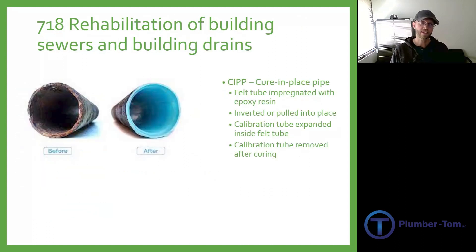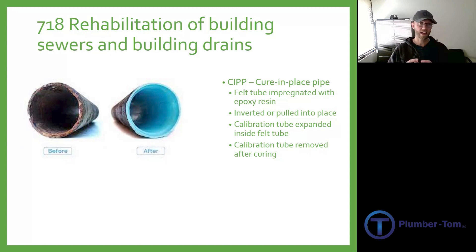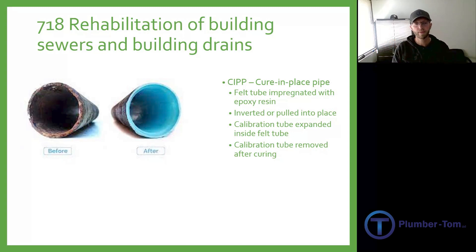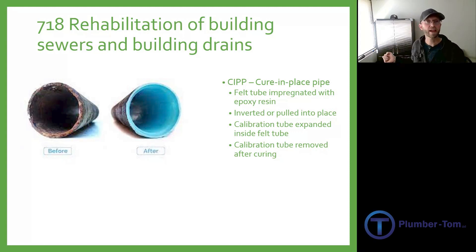Section 718.7 covers rehabilitation of building sewers and building drains using a cure-in-place pipe method. A felt tube containing epoxy is pulled in or inverted into the pipe. A calibration tube — basically a long balloon — goes inside and is inflated, pushing the epoxy against the walls of the pipe. It cures in place and the calibration tube is pulled back out, leaving the new epoxy lining adhered to the inside of the existing pipe.